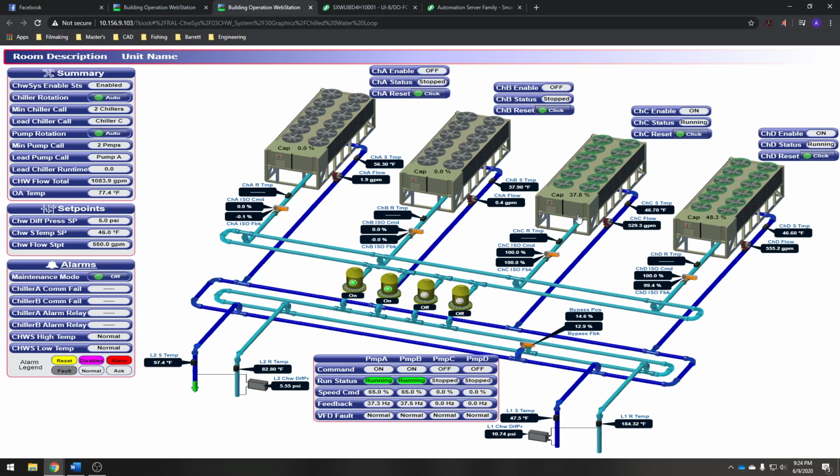We knew they were more than 550. But you only need 550, so if we were running at 900 GPM, you're just using extra energy, and you're still having pressure problems. So you're using more energy, and you're not accomplishing the objective of the data center, which is staying cool.